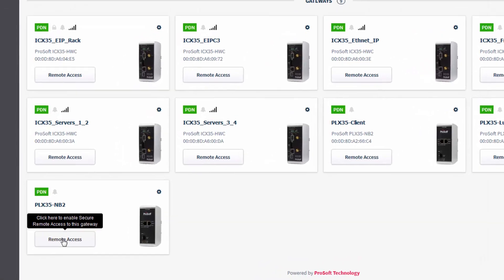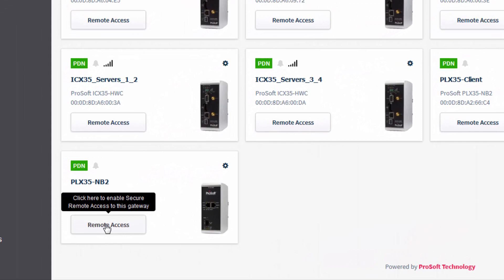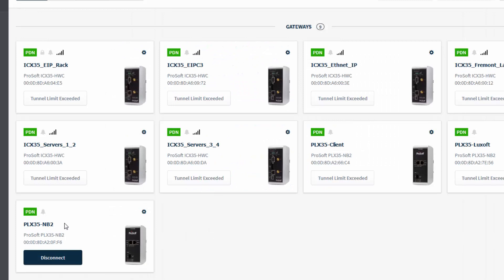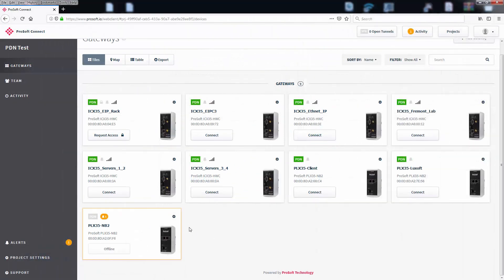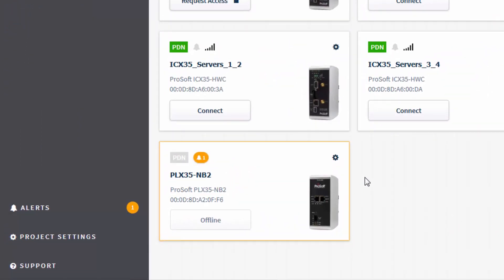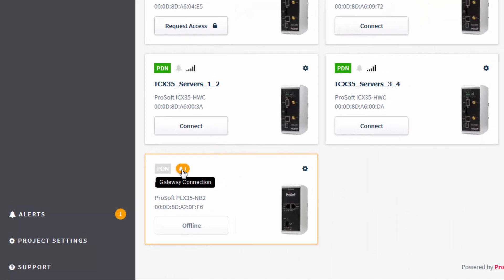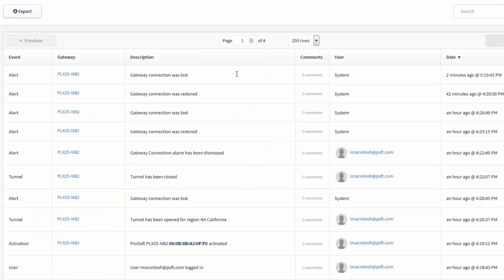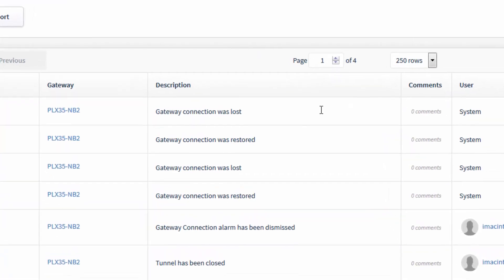If you need secure remote access to any of the gateways or their associated devices, just click the Connect button to open a secure tunnel to the devices behind a particular gateway. If PDN is not working — if there is a communication error with your cellular network, for instance — you'll see an alert on the project tile. The PDN icon will also be gray on the gateway tile. The activity feed will also record any communication errors with the gateways on the PDN.